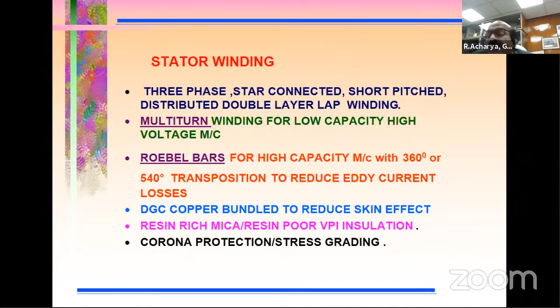And what you are seeing in the winding, or the stator winding, is basically a three-phase, star-connected, short-pitched, distributed, double-layer lap winding. Of course, I don't want to go into the details of this. If there is some interest, perhaps later on people can ask questions. But as of now, large capacity machines will have either three-phase star-connected windings, and the individual bars are either multi-turn type or Roebel bar type. Anything beyond, let us say, 100, 120 megawatt machines is with a Roebel bar design, wherein the individual strands are Roebel transposed, either 360-degree or 540-degree transposition, using DGC copper.